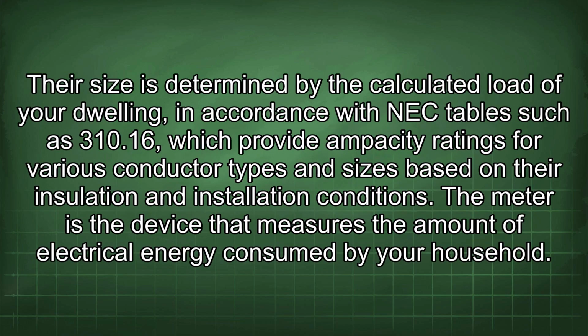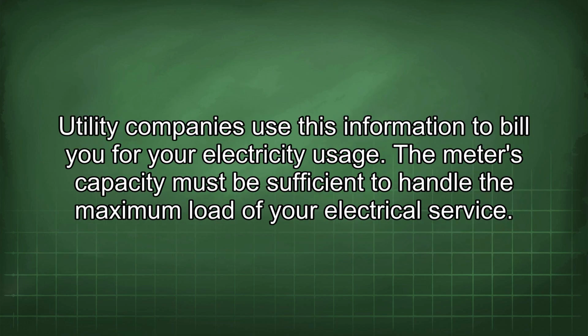Their size is determined by the calculated load of your dwelling, in accordance with NEC tables such as 310.16, which provide ampacity ratings for various conductor types and sizes based on their insulation and installation conditions. The meter is the device that measures the amount of electrical energy consumed by your household. Utility companies use this information to bill you for your electricity usage. The meter's capacity must be sufficient to handle the maximum load of your electrical service.